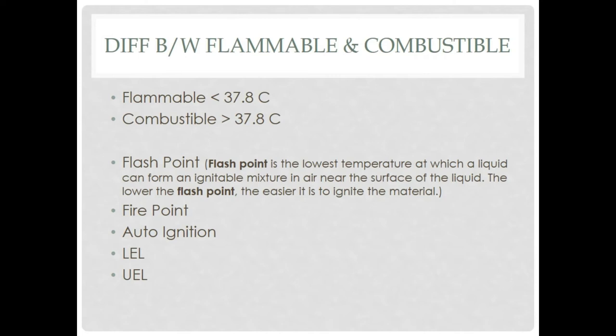Flash point is the lowest temperature at which liquid vapors or volatiles are found in the air or oxygen and make a mixture such that if there is a source of ignition, the material will ignite. In simple words, flash point is the lowest temperature at which liquid vapors evaporate and make a flammable mixture with air or oxygen which can easily cause fire with the help of an ignition source.